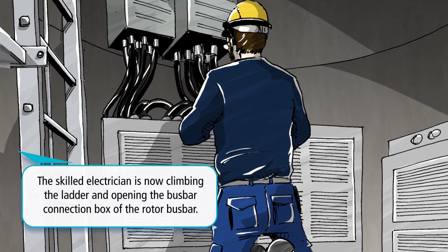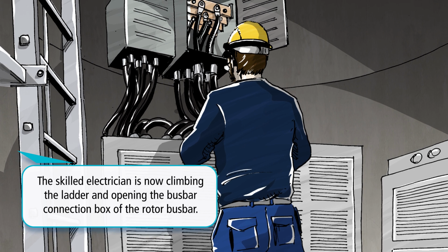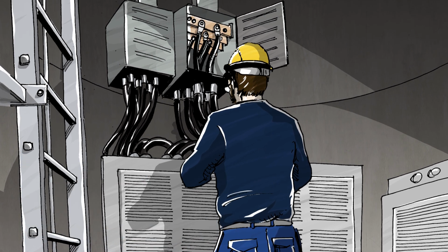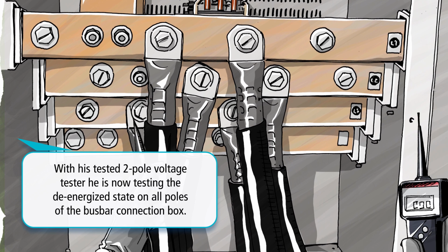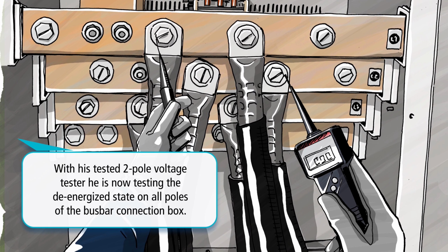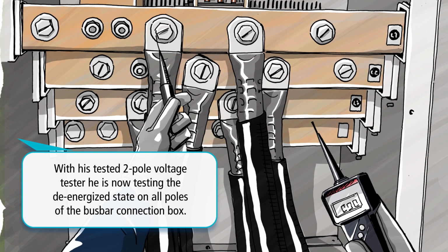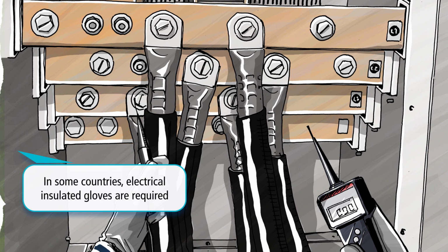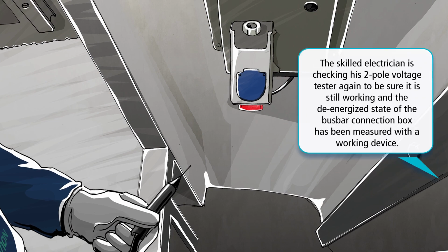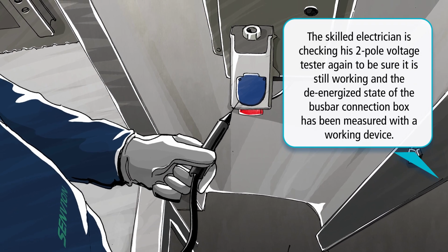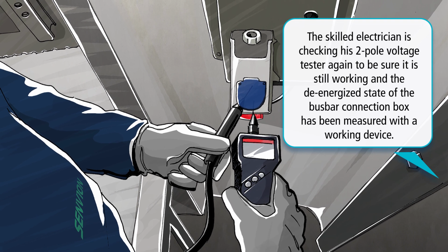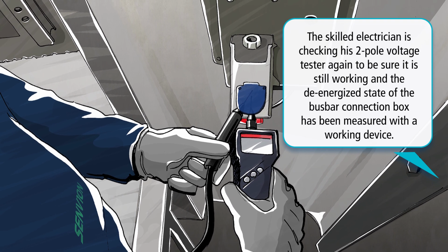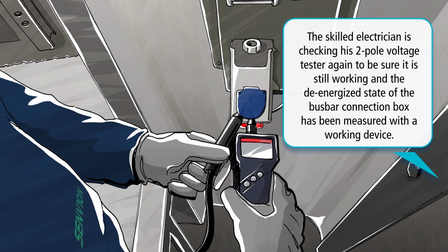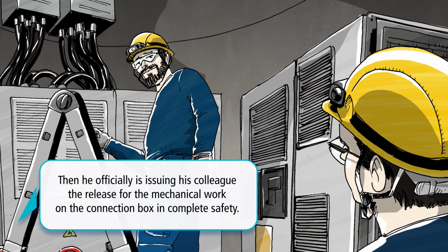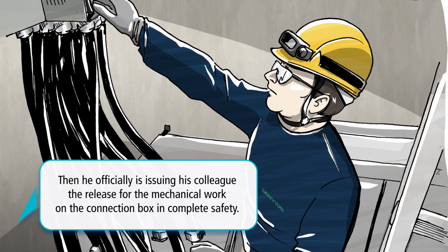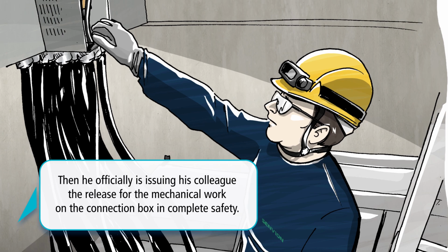The skilled electrician is now climbing the ladder and opening the bus bar connection box of the rotor bus bar. With his tested 2-pole voltage tester, he is now testing the de-energized state on all poles of the bus bar connection box. In some countries, electrical insulated gloves are required. The skilled electrician is checking his 2-pole voltage tester again to be sure it is still working, and the de-energized state of the bus bar connection box has been measured with a working device. Then he officially is issuing his colleague the release for the mechanical work on the connection box in complete safety.